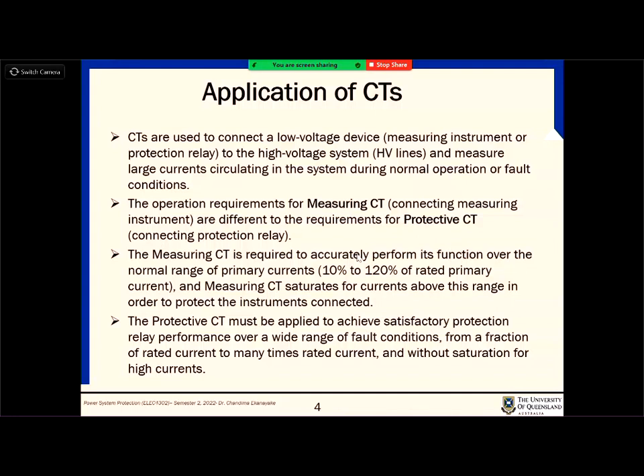Measuring, because measuring is quite important. You want to know whether the current is exactly at 1 amp or 100 amps, or is it 105 amps? Sometimes when the fault happens, it doesn't matter whether it is 105 amps or 108 amps. If it is overload, it's overload, right? So it's from the accuracy point of view, and the measuring CTs require very high accurate performance, but they don't need to perform well when there is a fault.